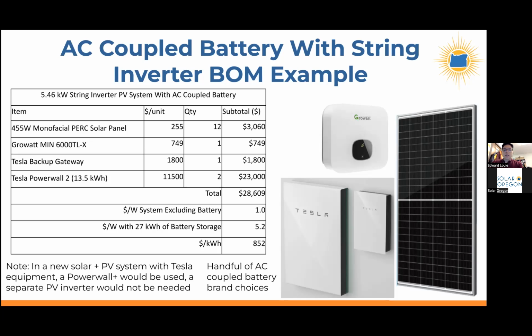How Tesla does this and still lets you operate your house during a blackout without electrocuting linemen trying to restore power on the grid, is they have something called a backup gateway, the smaller of the two wall-hung boxes. It contains electronics that sense when the grid is out during a blackout, and it automatically islands the house, meaning it disconnects the house from the grid.